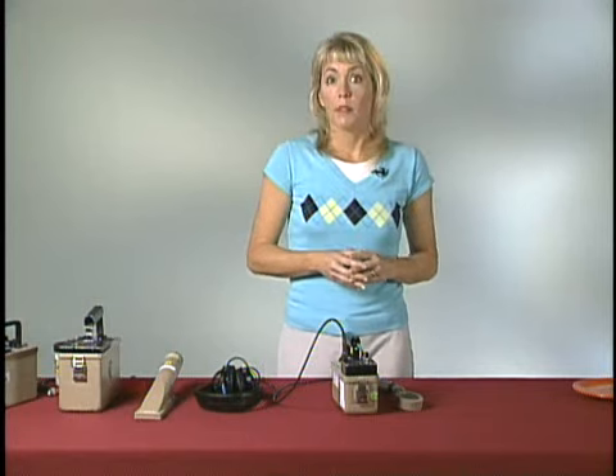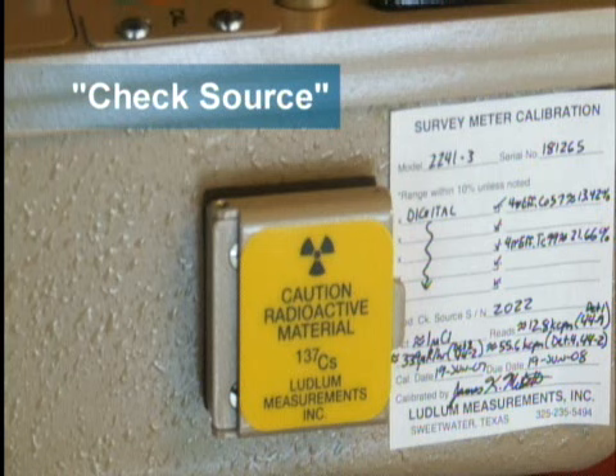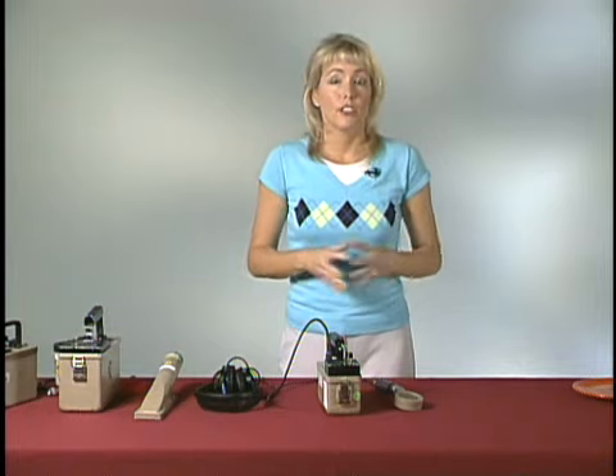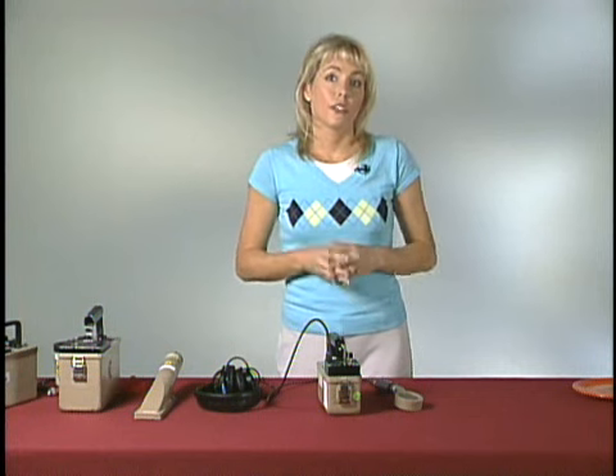Some rate meters come supplied with a convenient check source on the side and a label indicating what the meter response should be. In a pinch, if you need to use the instrument but you do not have a check source available, you can assume the GM is working properly if its response to background radiation is between 30 to 200 counts per minute. Depending on the environment and what type of building you're in, the background radiation level can vary. In the event of a radiation emergency, background radiation levels may be higher than usual because of environmental contamination.